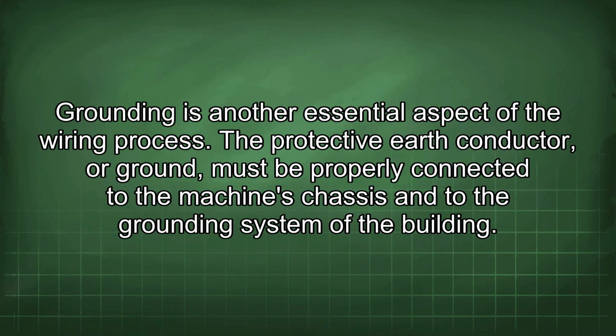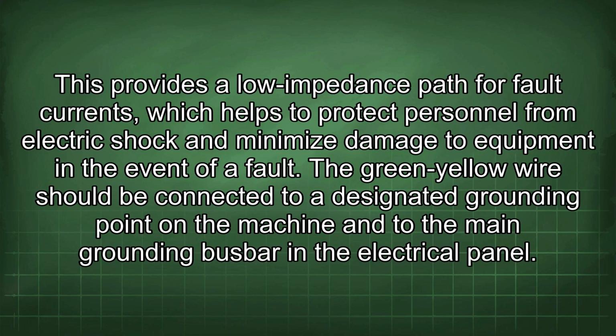Grounding is another essential aspect of the wiring process. The protective earth conductor, or ground, must be properly connected to the machine's chassis and to the grounding system of the building. This provides a low impedance path for fault currents, which helps to protect personnel from electric shock and minimize damage to equipment in the event of a fault.